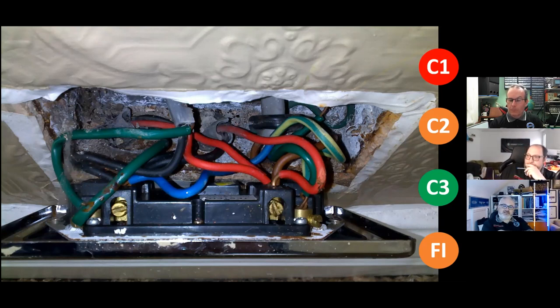Well, and that's the thing as well. It's observing the installation in use as well, isn't it? This is where the inspection and testing comes in, because you could find you put the socket back fine. And then you're going around doing Zs values, having confirmed polarity. But when you're putting your plug in, you then start to hear an arcing noise from inside, which may tell you that the screw has failed. It may have been damaged or something like that. And there is an arcing within that lug. That would then straight away make me go, I'm going to C2 that circuit.